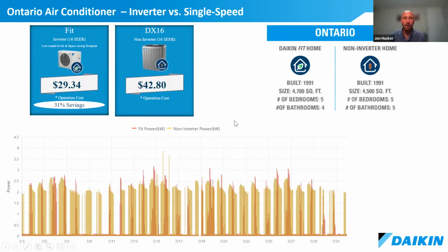And lastly, we've got Ontario. This is an air conditioner system, and this is on the higher end of savings, 31%. So again, if you're just looking at the impacts of an inverter, I think thinking about an additional benefit in the 20 to 30% range for a similarly rated piece of equipment is what the data is showing here.